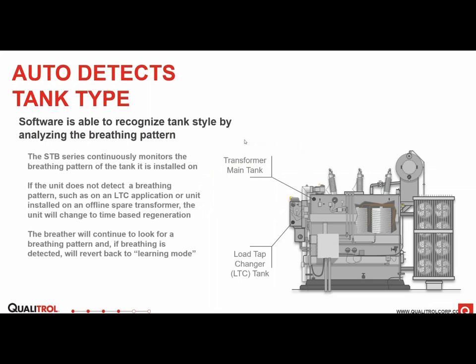Another big feature with the second generation breather from Qualitrol is that it's truly universal, in the sense that it can be applied on either the main tank conservator or the load tap changer conservator. Previously, some of you might have noticed, you would have a breather part number like an STB 101-1 TC, which stood for tap changer, because there are different firmwares for different breathing cycles. A tap changer might have a more sporadic breathing cycle than the main tank, because it's obviously less volume of oil, so it breathes a little quicker. It might not breathe all the time. Now, with the new breather, it can automatically detect what tank it is on and adjust the firmware accordingly.